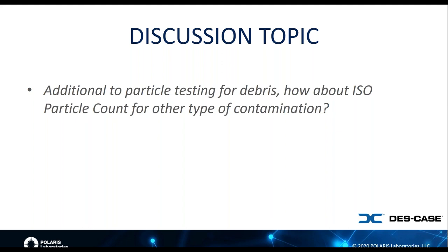Bob, would you add anything to that since you are in the lab? Yeah, we can do it that way. Typically, with our ferrographic analysis, we're more concerned with looking at wear contamination, but definitely while looking at a micropatch, we can see that there are other types of contamination. And we're typically going to lump that into either wear, abrasive particles or soft particles, depending on what we're seeing on the slides.